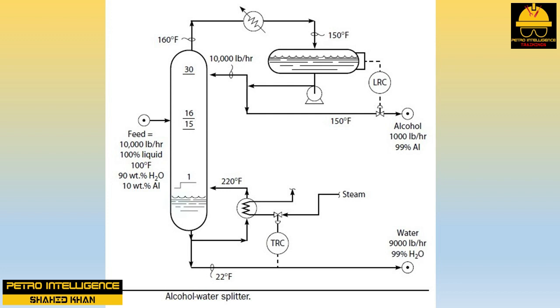But the liquid level in the reflux drum would begin to drop. The reflux drum level recorder controller (LRC) would close off to catch the falling level, and the overhead product rate would drop in proportion to the increase in reflux rate. We can now draw some conclusions from the foregoing discussion.